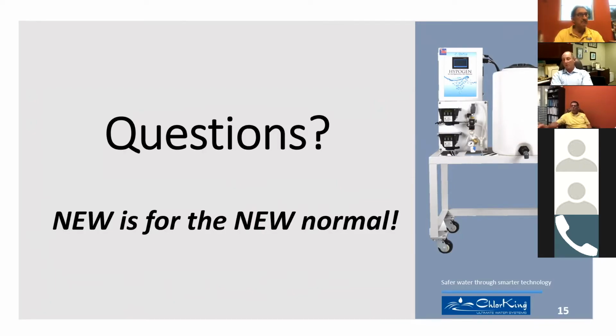What we have recommended, just because the solution is so cheap, is that if you don't use the solution at all and that tank sits there for 30 days without being used, dump it and restart if you're going to start using it. Once it's over 30 days old, dump it because it's so cheap. But as long as you're using some solution through the course of 30 days, we're automatically adding 1,000 ppm to that tank, so our dilution ratio is up. As long as you're using some solution during that course, 30 days is still fine.